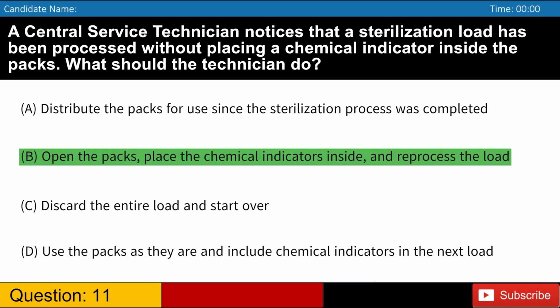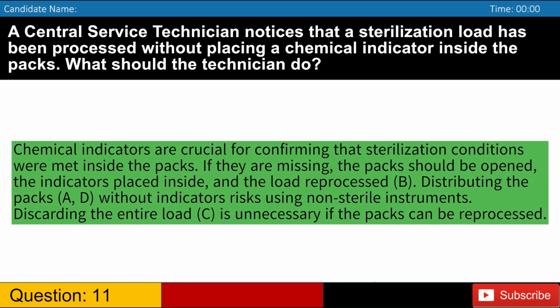Answer: B. Chemical indicators are crucial for confirming that sterilization conditions were met inside the packs. If they are missing, the packs should be opened, the indicators placed inside, and the load reprocessed. Distributing the packs, A, D, without indicators risks using non-sterile instruments. Discarding the entire load, C, is unnecessary if the packs can be reprocessed.